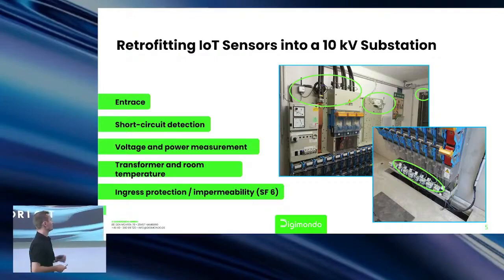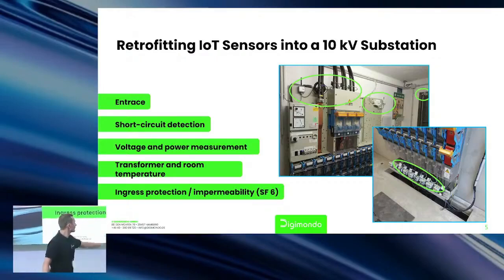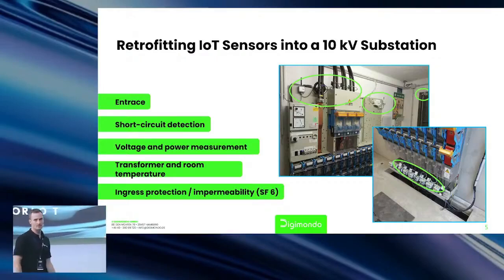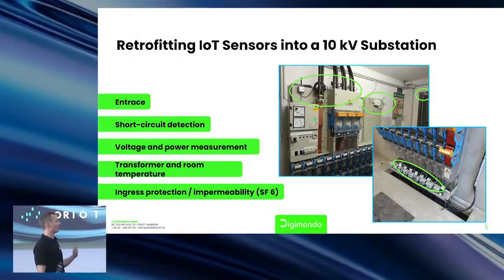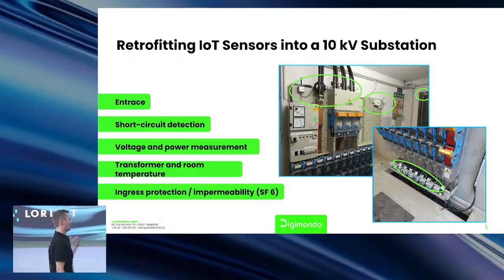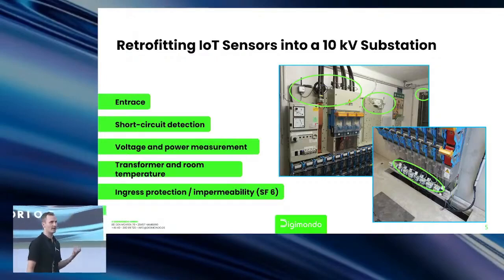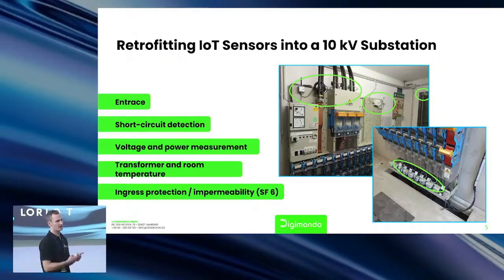As you can see in the top right corner, we installed a door sensor for monitoring the entrance, and of course short circuit detection. Sometimes you have to install a sensor for that, sometimes there's already a sensor where you can use an interface to get the data out of the substation. We also measure voltage and power, which I'll highlight later, and transformer and room temperature, because if that's rising, it won't take long before there's an outage. So you can act on that data and solve the problem.